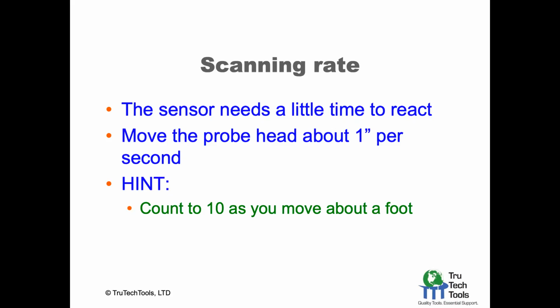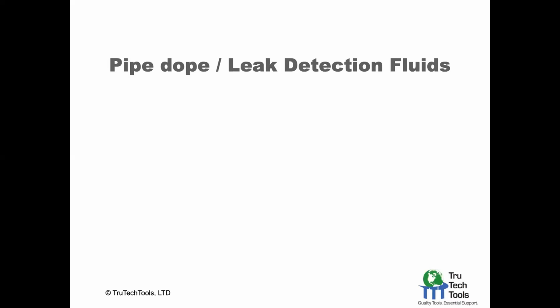If you hear the tick rate go up, or you see the display concentration go up, that means you're moving towards higher concentration. If it goes down, that means you're likely moving away from it. And also keep in mind that propane drops in blankets and methane rises. So be looking on the right side of the piping or valves or fittings or whatever as you move around to do your leak detection examination.